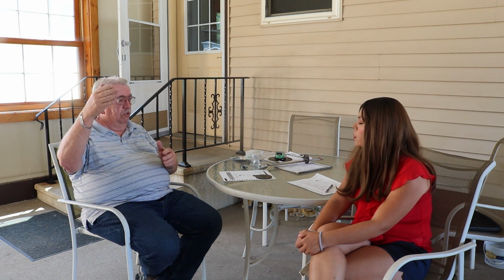because it takes your stove too long to recover. Okay. Not only that, on the Empyre stoves, the return line's coming back to the stove. Now, the way that Empyre stove is designed, where it burns in the front and it goes across those big ripples in the top of the stove, Okay. goes underneath that water baffle and out the back, that's also the coldest spot of the stove because that's where the smoke goes out. And if you're going to get any creosote buildup, where that return water comes in back of the stove, by dropping that temperature more than 15 or 20 degrees, you're going to start to build some creosote up back there.